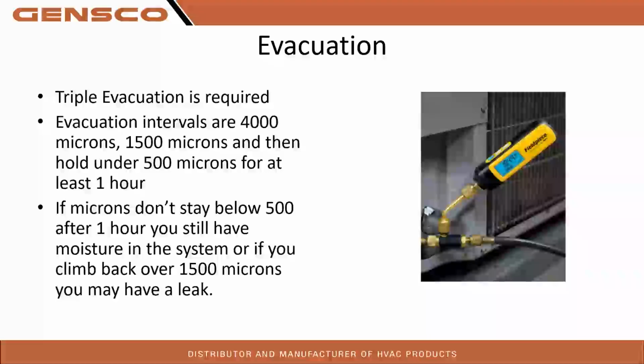If you have a system that has a lot of moisture in it, triple evac is going to be required. If you're working on an existing system and you open it up to repair a leak or replace a part, triple evac is going to be required.